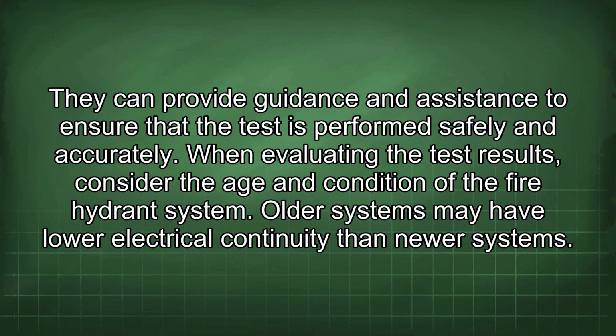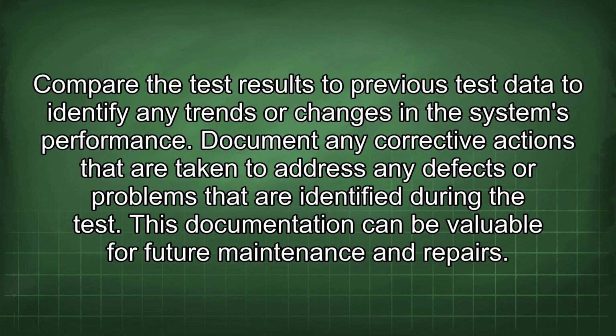When evaluating the test results, consider the age and condition of the fire hydrant system. Older systems may have lower electrical continuity than newer systems. Compare the test results to previous test data to identify any trends or changes in the system's performance. Document any corrective actions that are taken to address any defects or problems that are identified during the test. This documentation can be valuable for future maintenance and repairs.